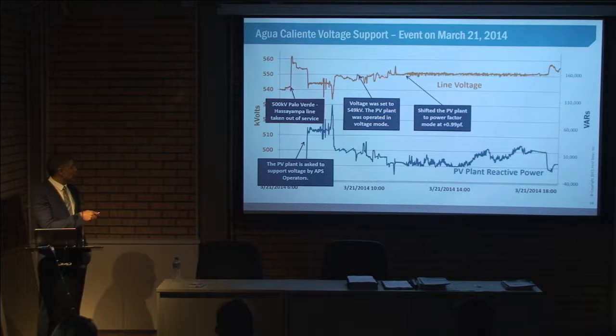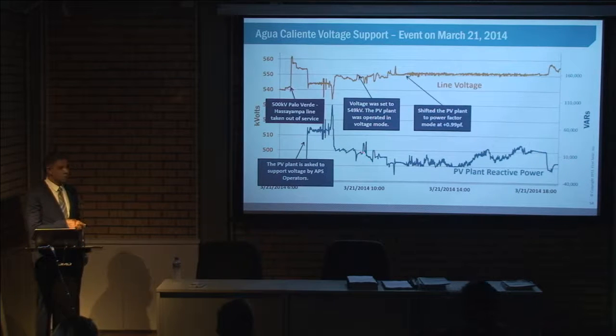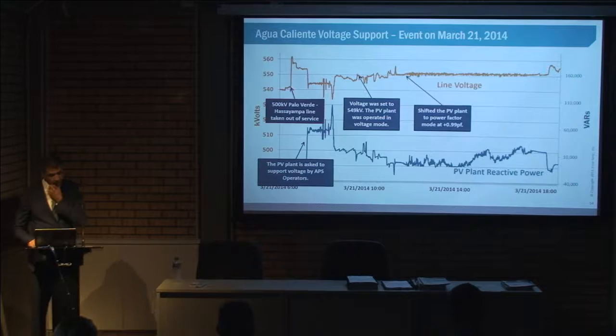Once it stabilized, we switched to power factor mode at 0.99%. This was possible because the power plant was properly designed and we were able to inject reactive power. You can see the reactive power fluctuating as we tried to bring the voltage down and keep it stable.